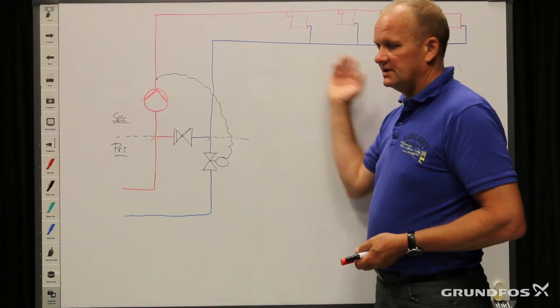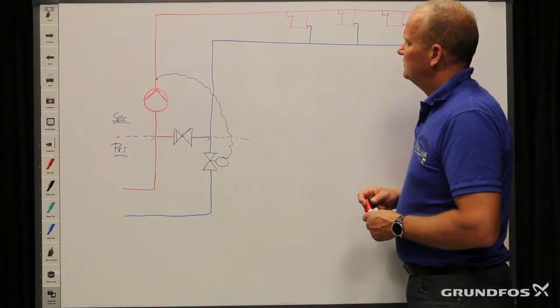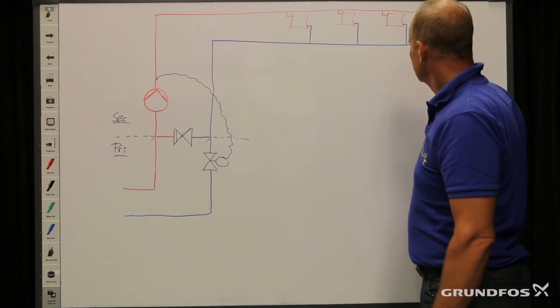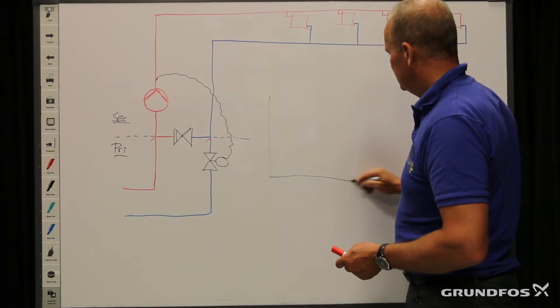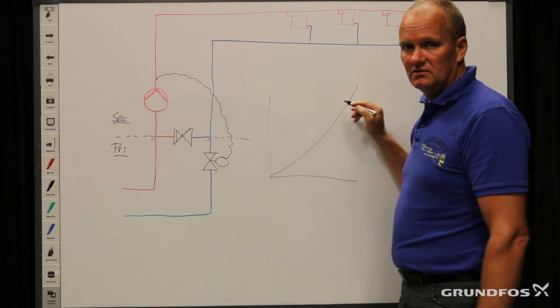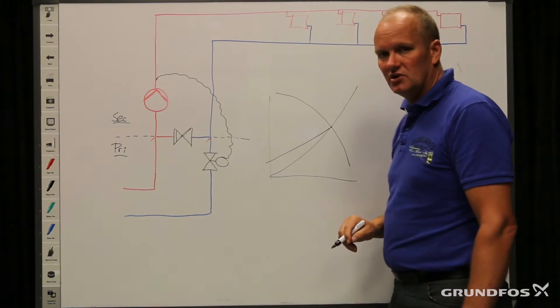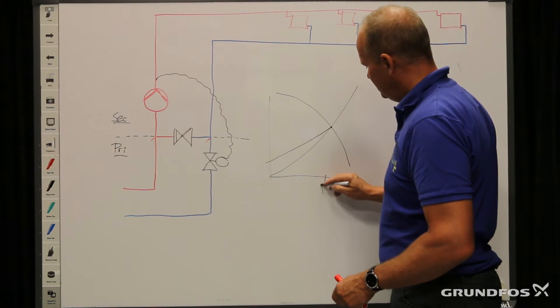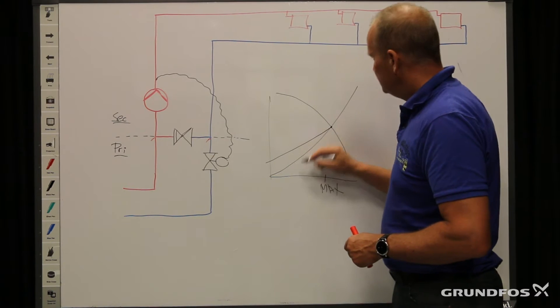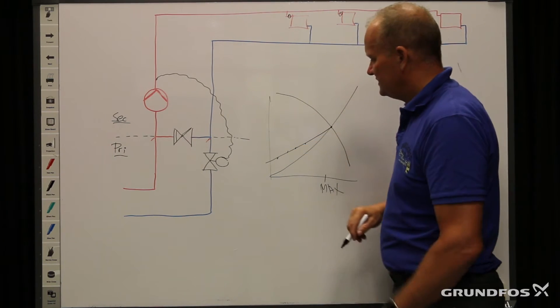Applications like this can be seen in widespread radiator systems. It could also be air handling units, cooling coils, or similar. If we have a widespread system where there is a long distance from the pump to the final consumer, then the pressure loss will increase exponentially — meaning the greater the flow, the pressure resistance will rise in second proportion. For that reason, when we connect that to our pump, we would typically choose proportional pressure, because at maximum flow level we will have the exact pressure needed.